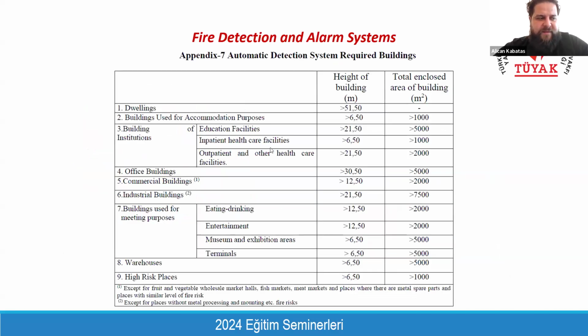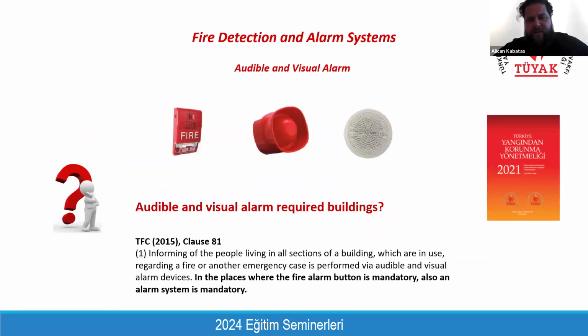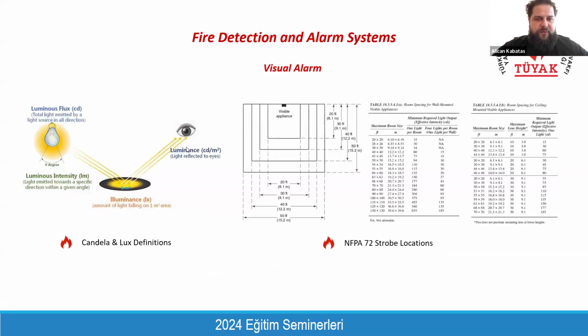An automatic detection system is becoming mandatory according to this table. It is Appendix 7 of the Turkish Fire Code. You can see it in the Turkish Fire Code as well. And we have some audible and visual alarm systems. We need to provide this system, and especially strobes, not speakers, are not preferred by architects, but we need to have them according to the Turkish Fire Code and also according to the international standard.